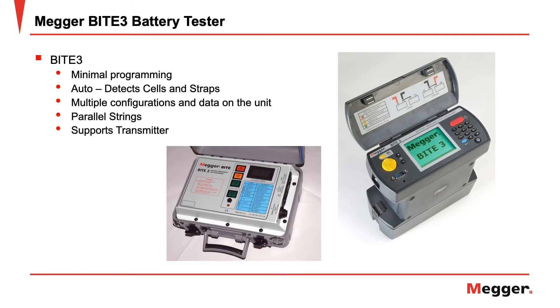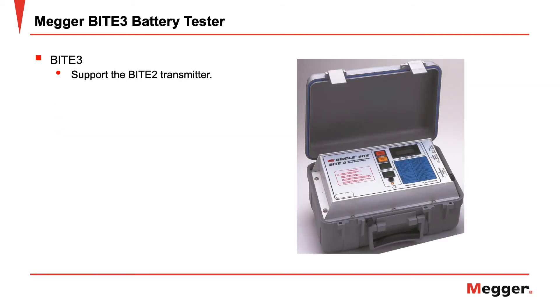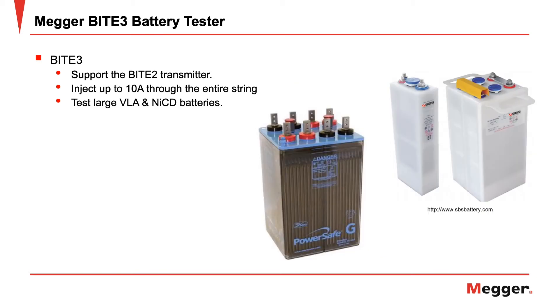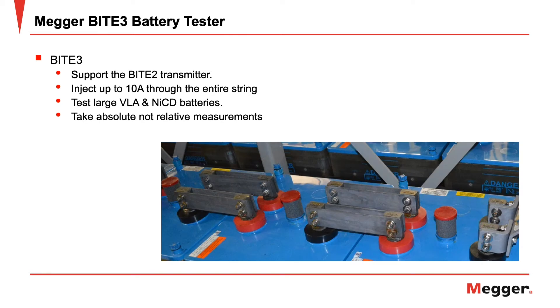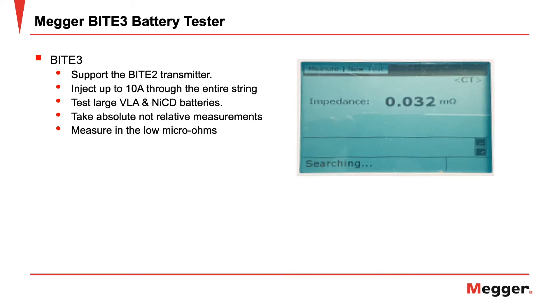The BITE 3 can also be used with an external transmitter, allowing you to test large VLA cells. The BITE 3 supports operation with a BITE 2 transmitter, which injects up to 10 amps through the entire string, allowing the BITE 3 to take high-resolution measurements — even for the largest VLA batteries. You will also be able to take absolute, not relative, measurements of bar-type intercell connections, measuring down into the low micro-ohms.